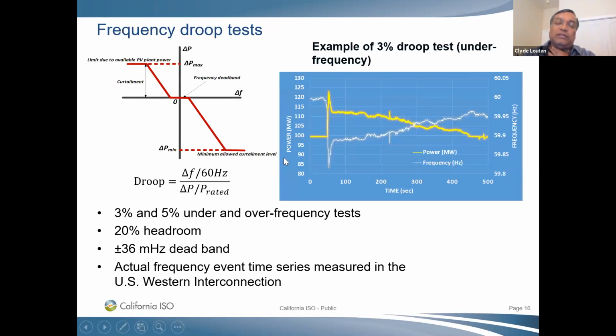This plot here shows a couple of things. One, this was an actual low-frequency event, which is this white plot. So for an actual low-frequency event, we wanted to see how well this solar plant could respond, not only for frequency regulation, but also for frequency response. So some of you that are familiar with the inertia timeframe, like in the Western interconnection here, we see minimum frequency within 8 seconds following a disturbance. Well, this plant, depending on how fast you set that droop setting, you can see how quick this solar plant was able to respond, which is that yellow. So you can also respond within the fast frequency response timeframe. So if frequency response is an issue, let's say you do not have a lot of inertia on the system, solar plants can help you in that transient period.